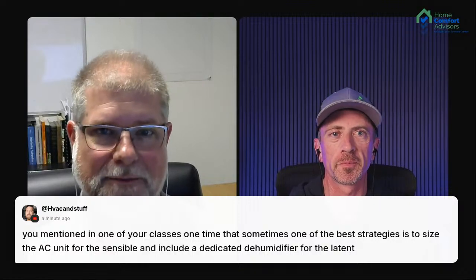Yep, that's exactly what I'm referring to. If you let the AC system do its own thing for dehumidification, it's dependent on whether the thermostat's calling for cooling, whether it's a heat pump or a straight air conditioner. If there's no load in the house, the thermostat won't call for cooling, which means there's no dehumidification. So handling those two systems separately costs more money, but the outcomes are so much better.